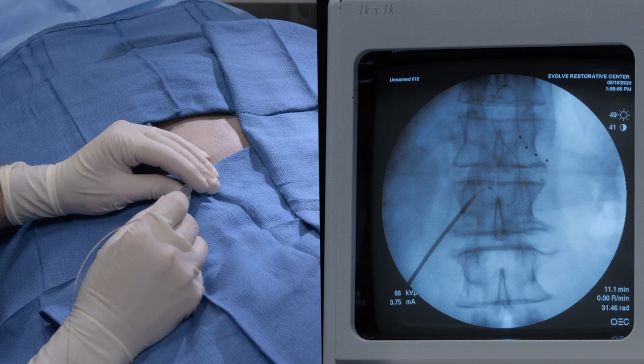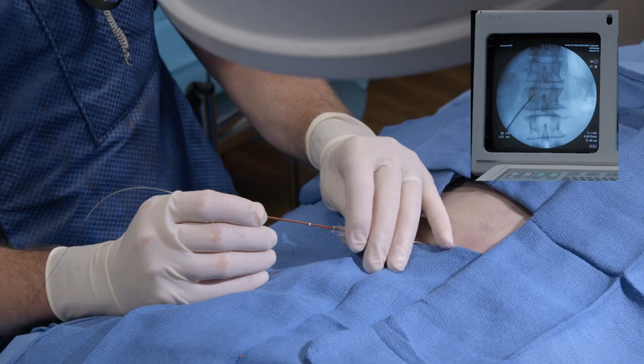Now, ideally, you really don't want the lead to be going past the vertebral body above and below, because if you're going to do multiple levels, you want to have some room. You obviously want to start with the most superior level first. Now, to remove this, you have to be careful, removing the needle first, because the sheath is much longer than the needle. And now, very carefully, he's advancing the lead through the sheath while he's retracting the needle and the sheath simultaneously.